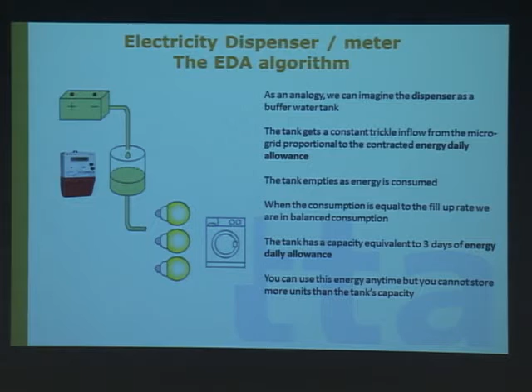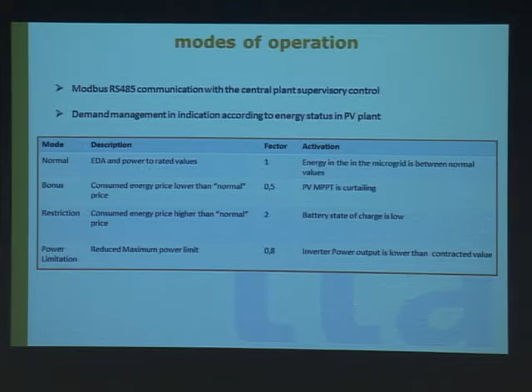So you can add a Modbus communication, and then according to the plant status you could change the price of that electricity — each watt hour could cost 2 units or 1 unit. This gives flexibility, and you could also limit the power: if the microgrid is reaching the maximum power of the inverter, you could reduce the maximum power to the houses.